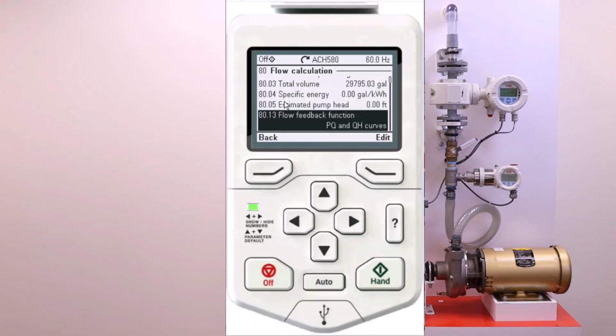That's very important. We need 8005 because that is, when the drive is running, the estimated pump head that is being calculated. If I was to start the drive up right now, it's showing estimated pump head as the drive speeds up to 60 hertz. And at 60 hertz, my estimated pump head is 38.57 feet. 60 hertz, 38.57 feet. That's my estimated pump head at this time at 60 hertz. So I can stop it.